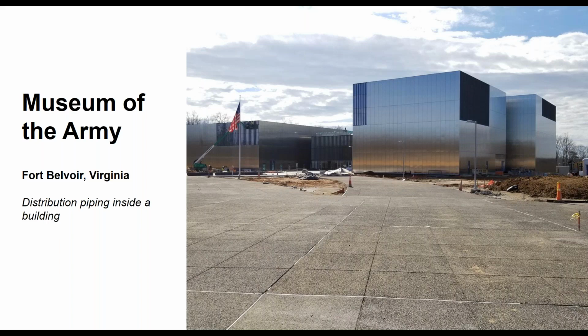This is radiantly heated and radiantly cooled, a similar process where they didn't want overhead piping. They've got 24 different manifolds scattered throughout the building for heating and cooling, fed by INSULPEX that was buried beforehand. A bit different use case, but similar, since you don't want a steel piping distribution line to drip on top of documents and things that cannot be replaced. A tank can get wet, but probably not a very historic Army document in a glass case.